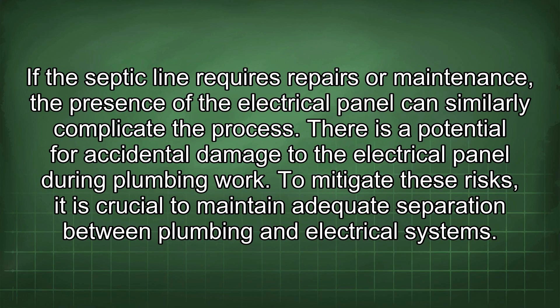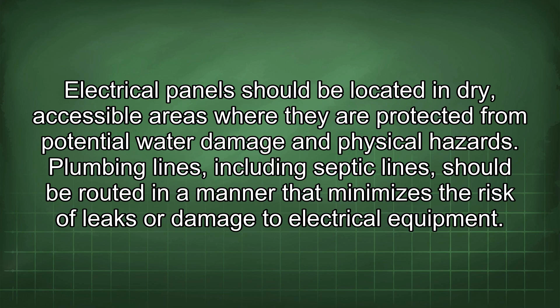To mitigate these risks, it is crucial to maintain adequate separation between plumbing and electrical systems. Electrical panels should be located in dry, accessible areas where they are protected from potential water damage and physical hazards. Plumbing lines, including septic lines, should be routed in a manner that minimizes the risk of leaks or damage to electrical equipment. Building codes often specify minimum clearances between plumbing and electrical installations to ensure safety and prevent interference.